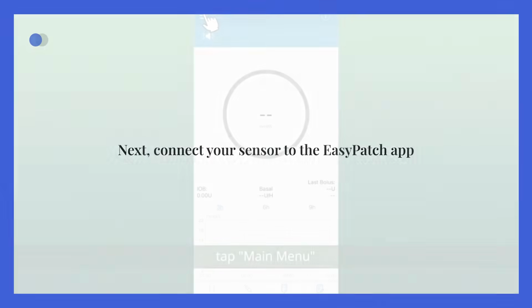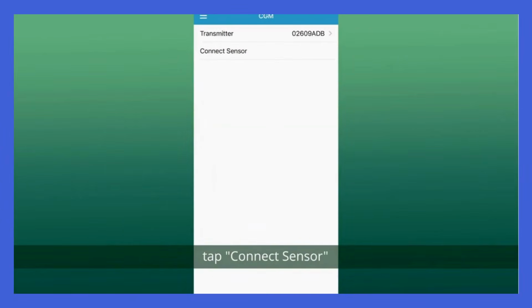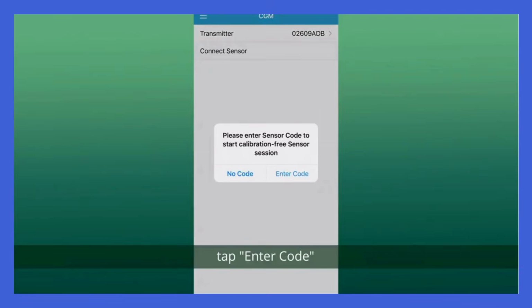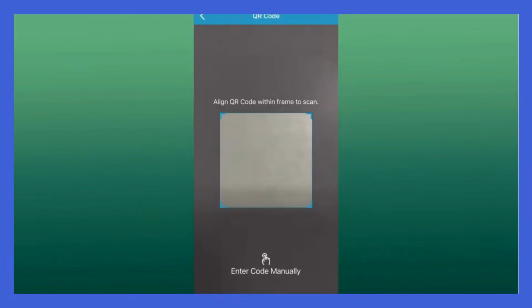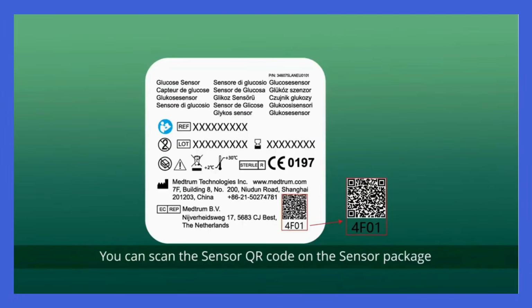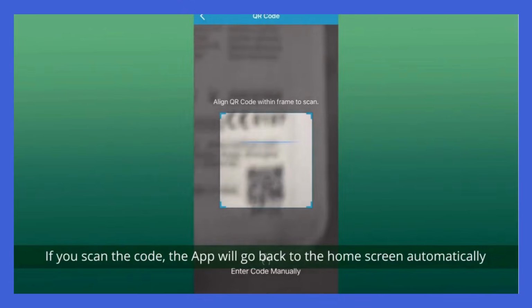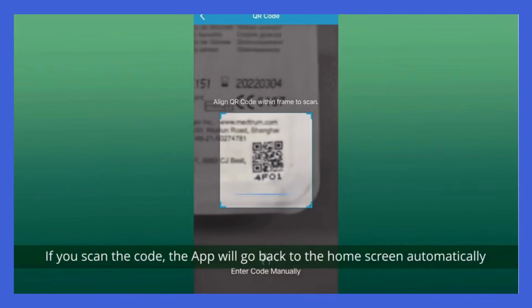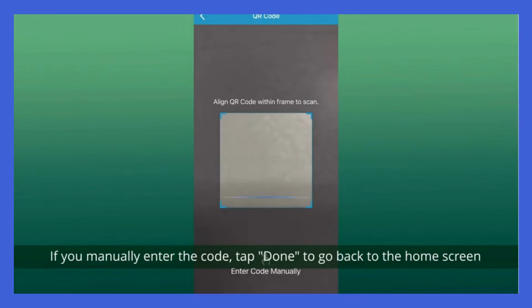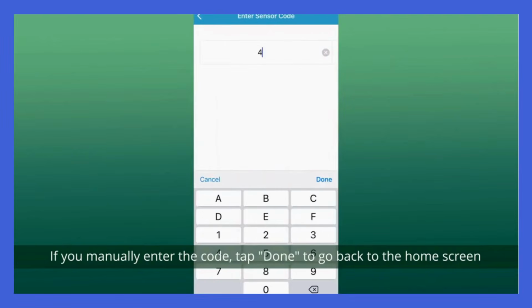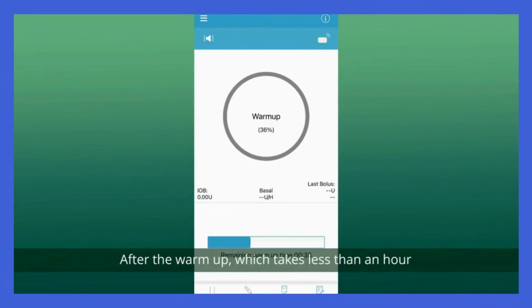Next, connect your sensor to the EasyPatch app. From the home screen, tap Main Menu, tap CGM, tap Connect Sensor, tap Enter Code. You can scan the sensor QR code on the sensor package or manually enter the sensor code. If you scan the code, tap OK to confirm the code is correct and the app will return to the home screen. If you manually enter the code, tap Done to go back to the home screen. Next, apply your TouchCare Nano sensor and transmitter on your skin if you haven't done so. After the warm-up, which takes up to 30 minutes, you will receive glucose readings.